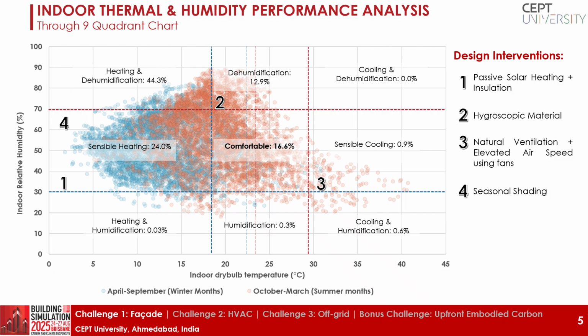Using a 9-quadrant analysis chart based on the ASHRAE 55 adaptive comfort model, we found that only 16.6% of bridge hours lie within the comfort zone, while 24% require sensible heating and nearly 13% need dehumidification. Seasonal trends show a strong heating demand during the winter months from April to September, with only minor cooling and humidity control requirements in summer.